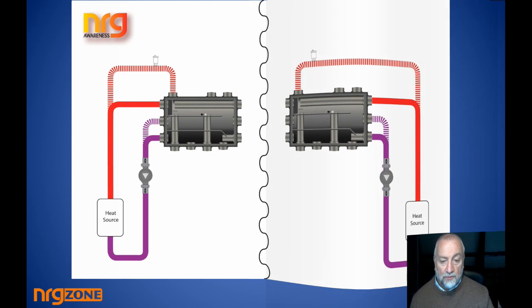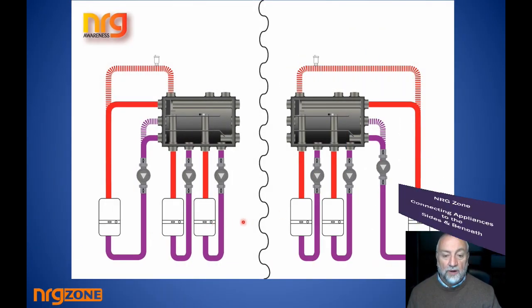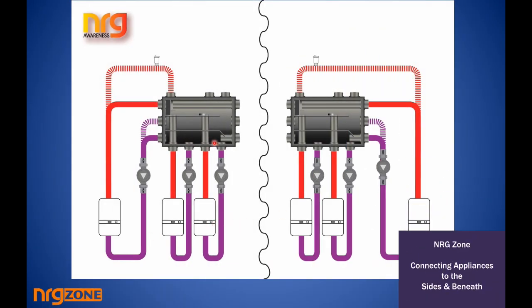If you're putting boilers underneath the unit, you come from the lowest chamber, deliver heat up to the top chamber, lowest chamber up to the top chamber. So here now we have 3 boilers collecting heat. In fact, if this dotted line was a 4th boiler, you could have 4 boilers, provided that the heat being delivered in can be taken away by the connections on the right hand side. And remember, this connection and this connection are right next to each other, so there's no reason why you can't tee them together. And this connection and this connection are right next to each other, so there's no reason why you couldn't tee the 2 of these together.